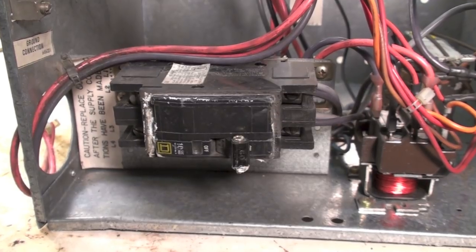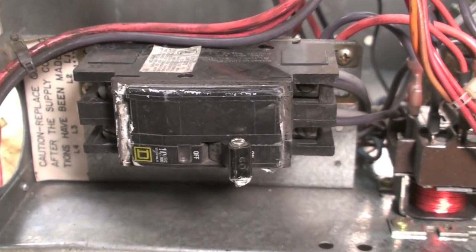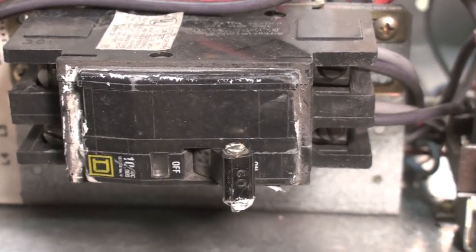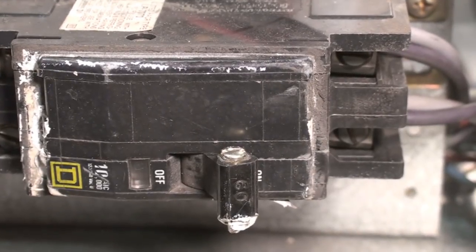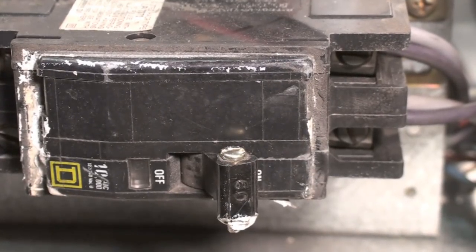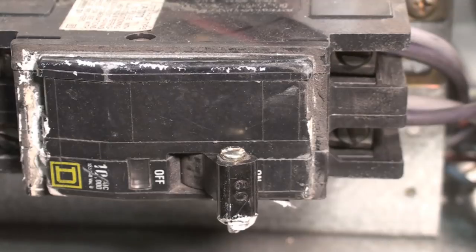That's the breaker. There could be double breakers. This is 240 volts. There could be any number of these in here—two, three, four—depending on how many elements you have. This one has two elements, so it'll be 10 kilowatts.